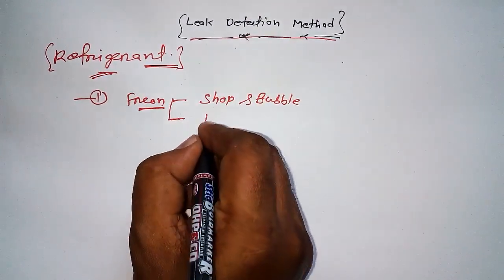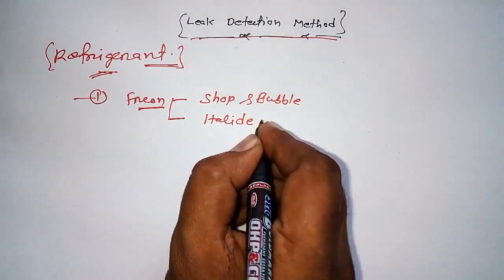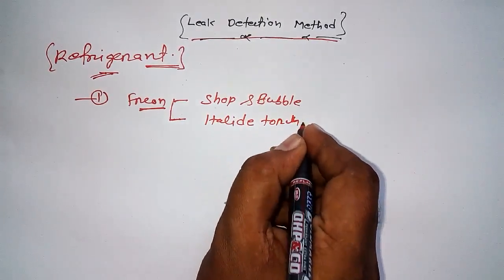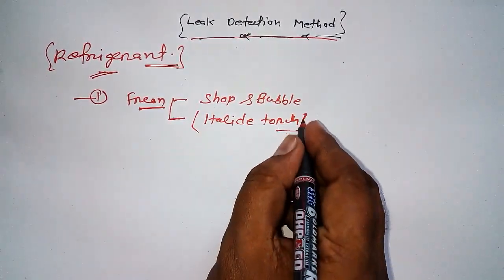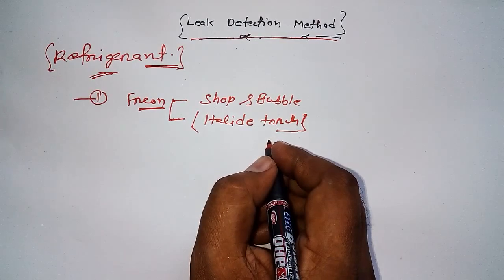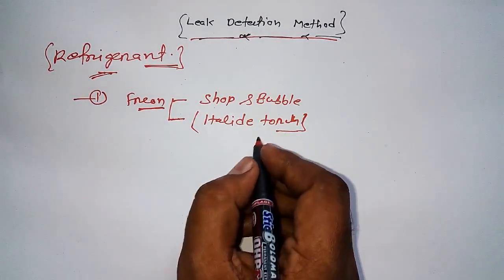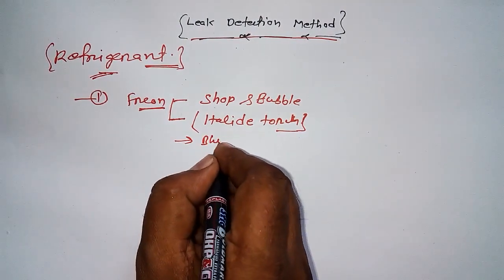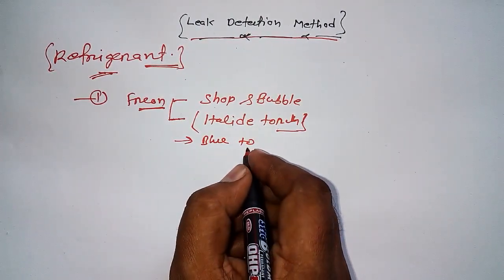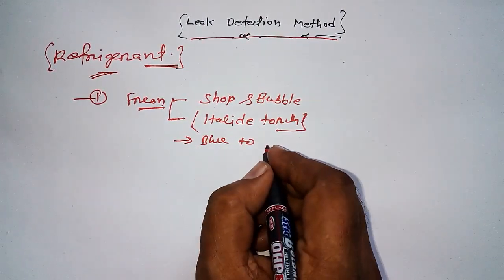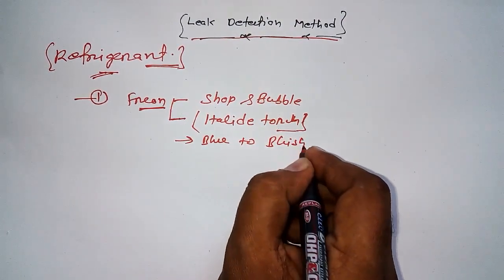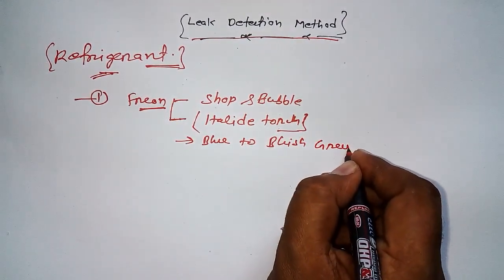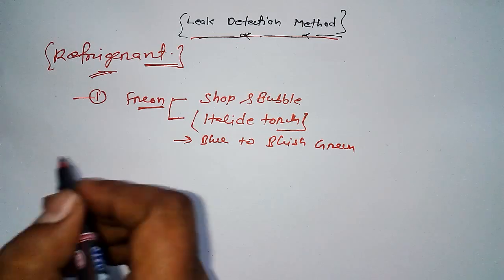Another method is halide torch. If you have a halide torch, then we can easily detect the leakage of freon because we get blue light. If leak is detected, then blue will be converted into bluish green. This is how we can detect freon refrigerant.